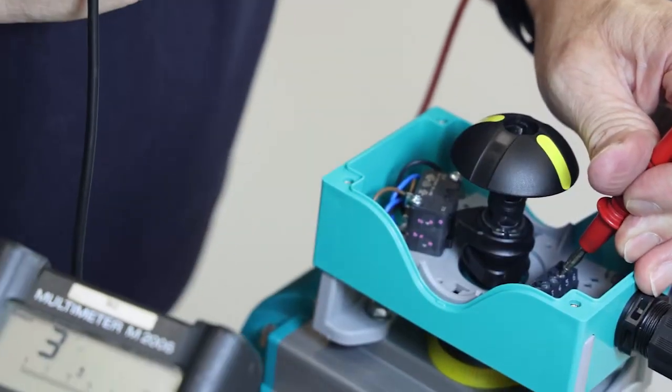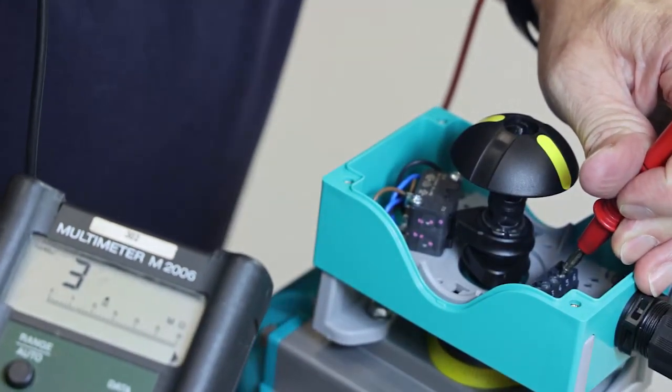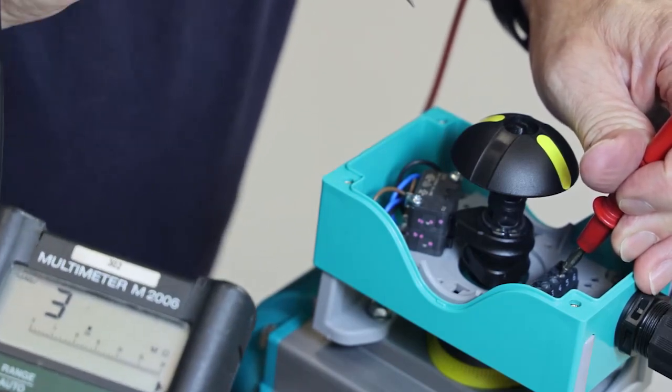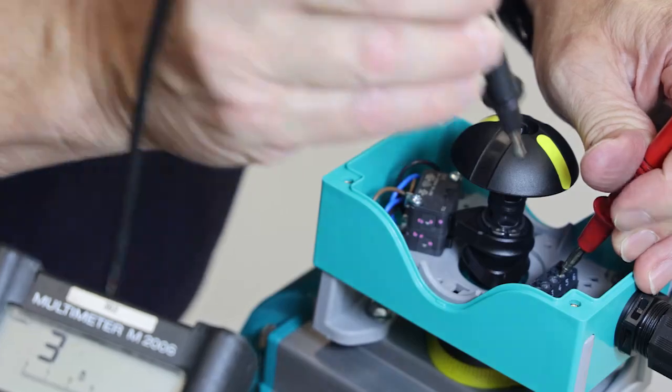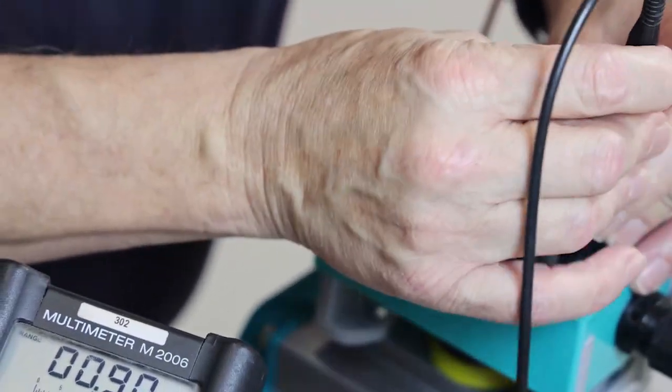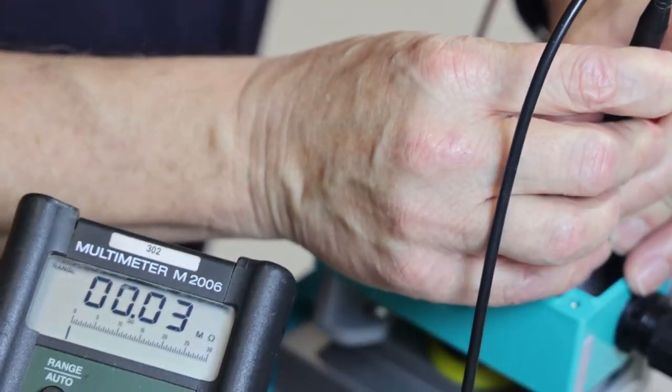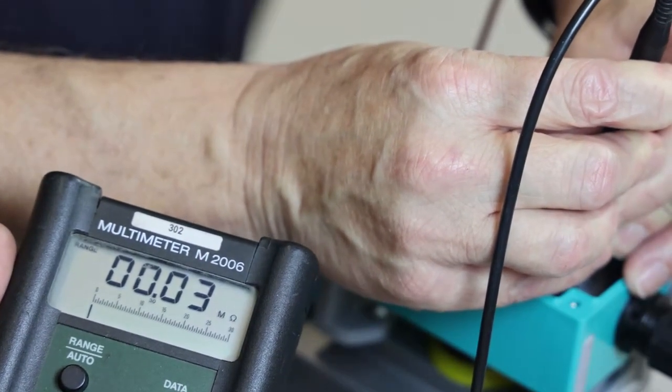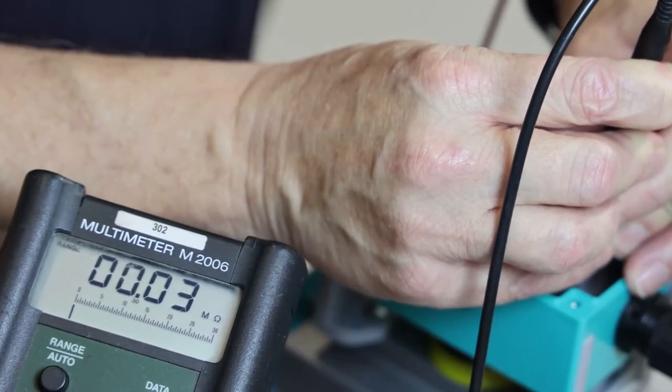The valve is now open. We check with terminals four and five if the cam is properly set. As we see on the multimeter, we have no resistance, so we can say the valve is properly set.